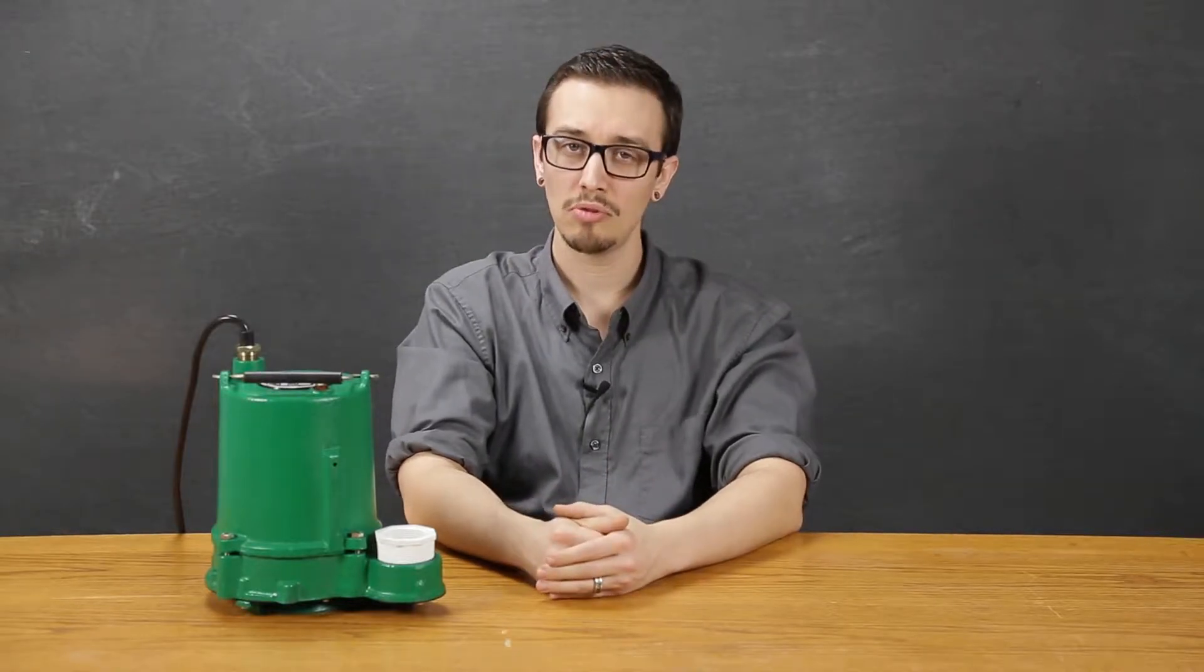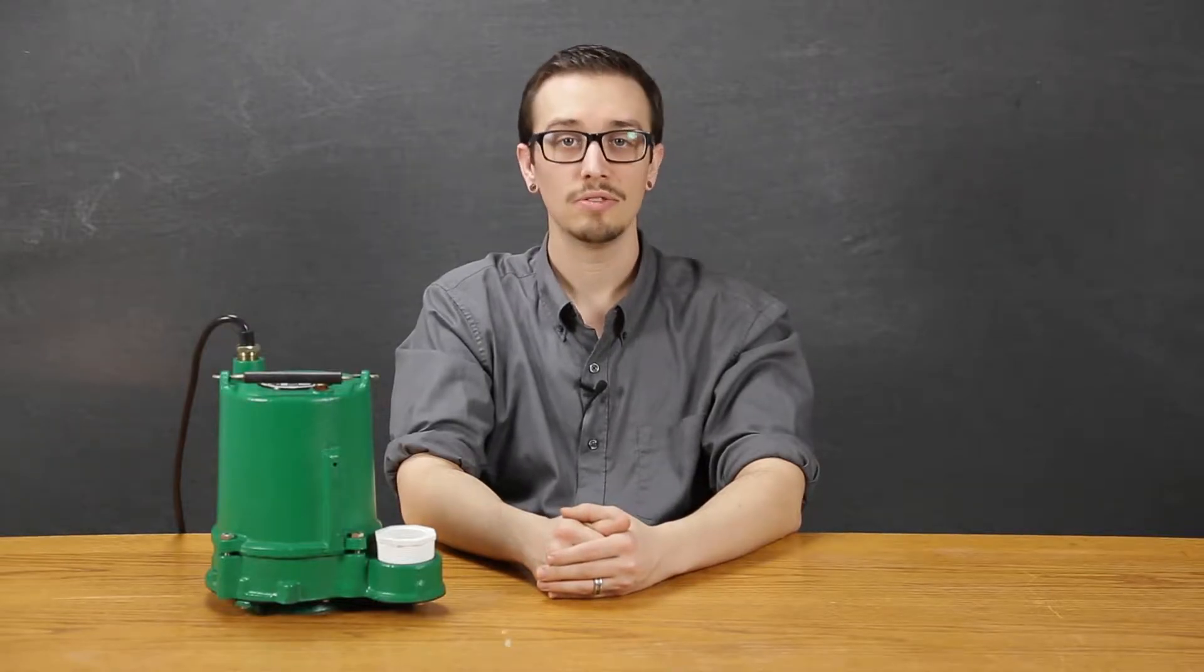As a standard, the motor rotates at 1750 rpm and these pumps can produce 25 foot of head and a maximum flow of 60 gallons per minute.